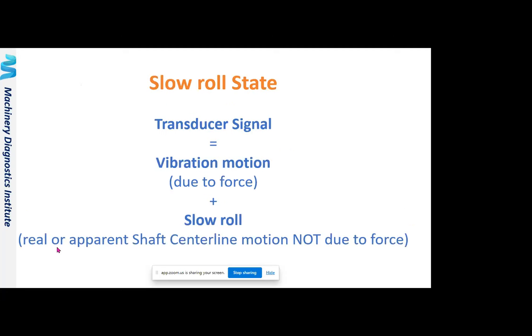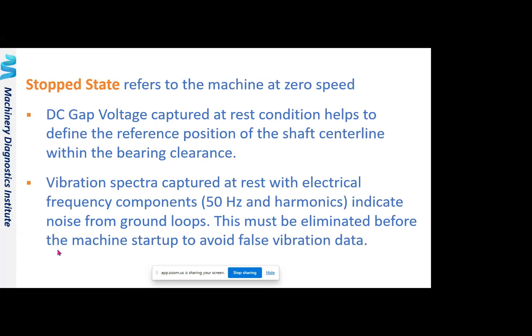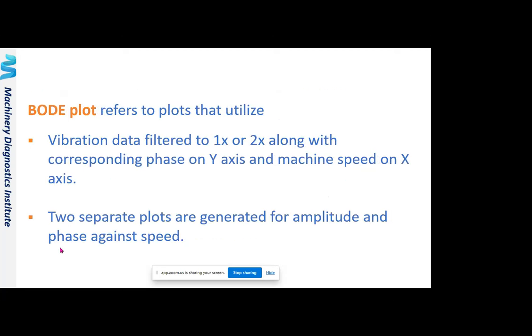Under normal conditions, the transducer signal consists of vibration motion from dynamic forces plus slow roll noise from shaft irregularities. To identify actual vibrations, you must subtract the noise from the signal — that is where slow roll data comes in. In the stopped condition at zero speed, DC gap voltages are captured, helping to understand how shaft centerlines are positioned in the bearings under normal operating conditions.